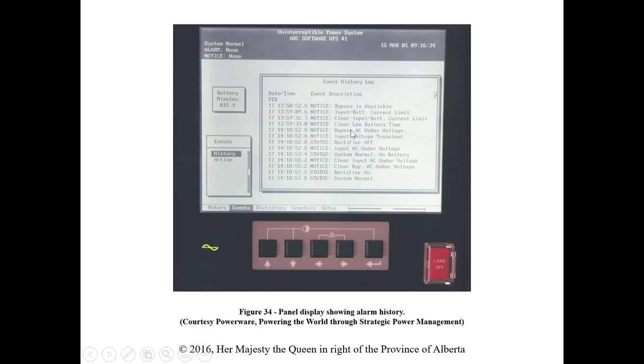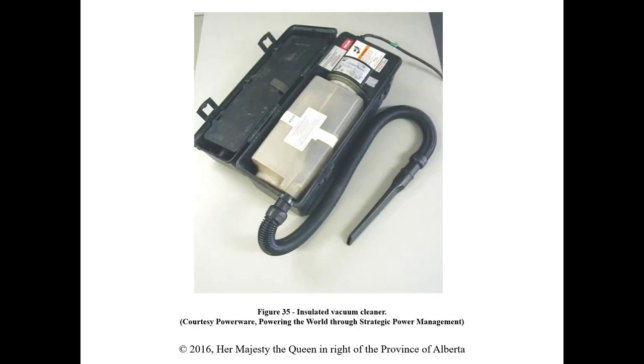The alarm history log shows events such as bypass availability, low battery, and bypass activation due to under-voltage. As a maintenance operator you can review this log to see how the system has been performing. Maintenance also involves using an insulated vacuum for cleaning, with anti-static precautions to avoid shorts across electronic equipment. Some technicians spend a full day cleaning the UPS system and testing batteries to confirm they are in good working order.